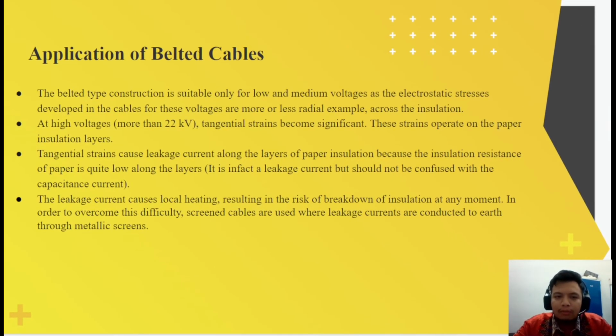Next, I will talk about the application of belted cable. So there are four main points. First, the belt type construction is suitable only for low and medium voltage, as the electrostatic stresses developed in the cable for this voltage are more or less radial across the insulation.